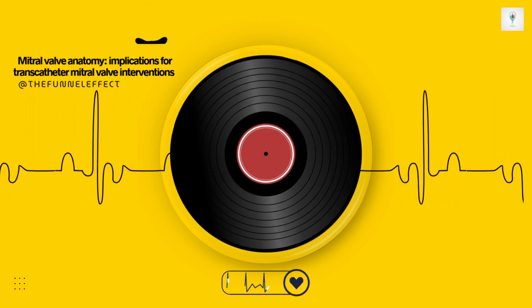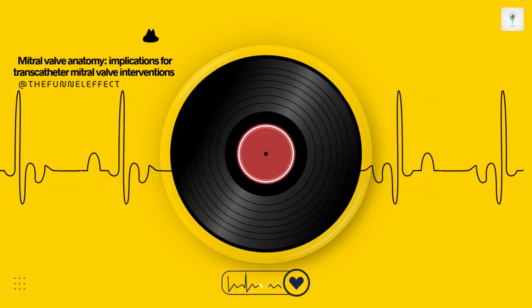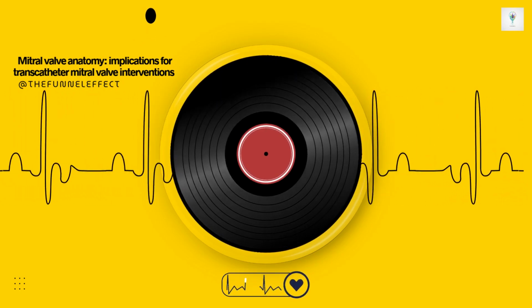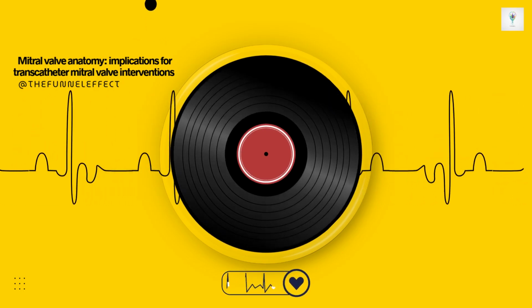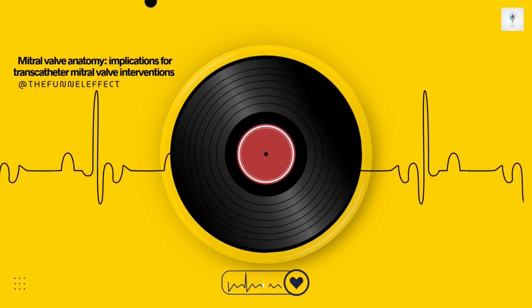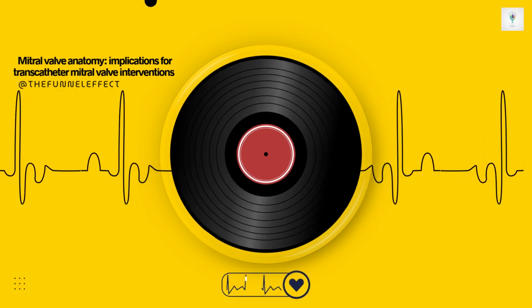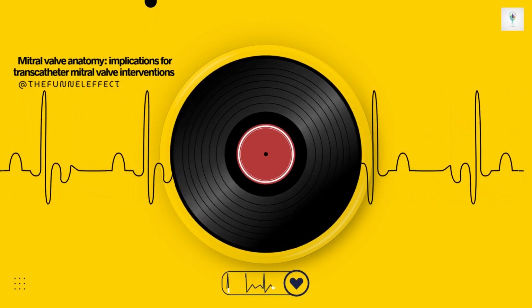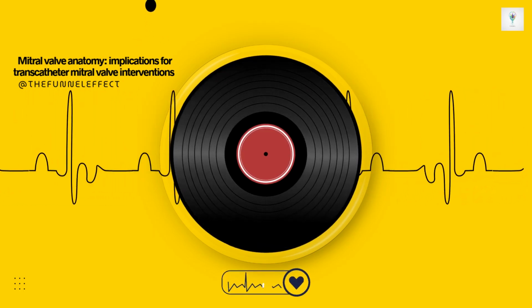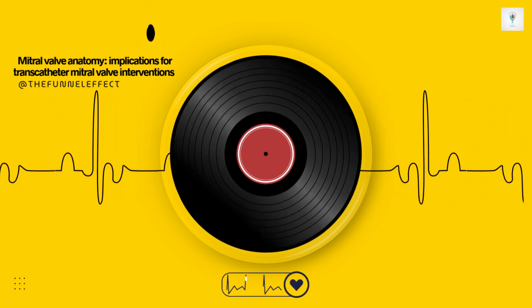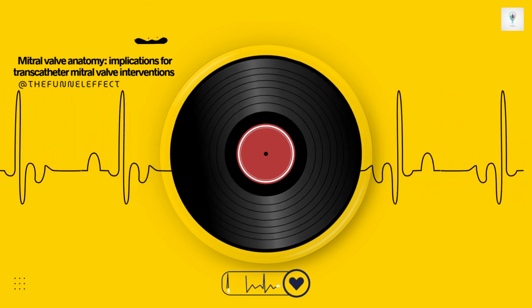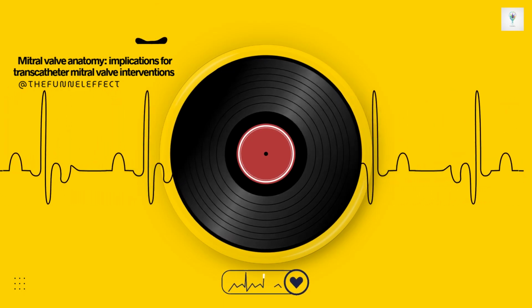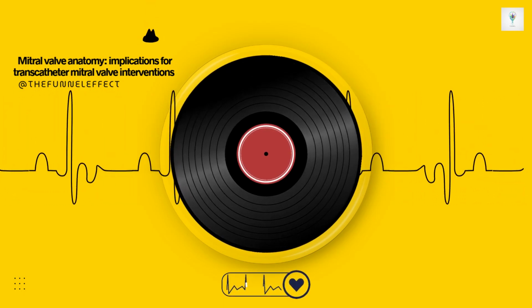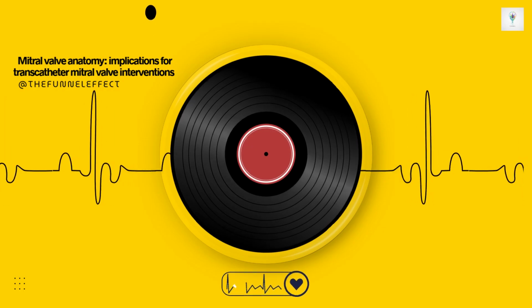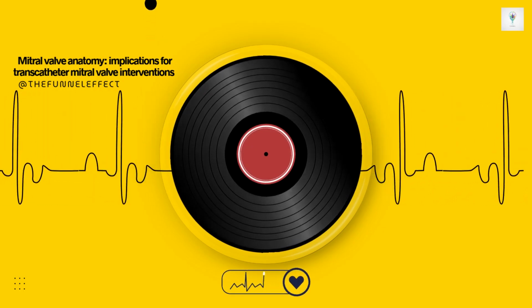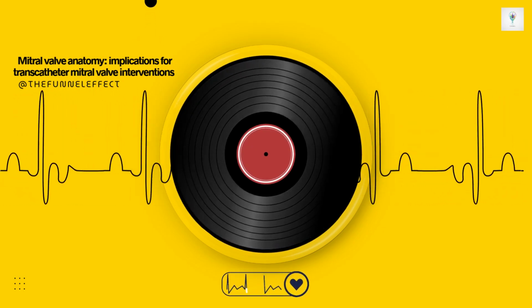The MV annulus is D-shaped, not circular. It's highly dynamic, changing shape and size constantly. It's saddle-shaped, non-planar. And especially posteriorly, it lacks firm, fibrous tissue to anchor into. So getting a prosthetic valve to sit securely and seal perfectly in that moving asymmetric ring is tough. Extremely tough. You need significant radial force from the valve frame to hold it in place, but too much force risks damaging surrounding structures. Finding that balance and achieving a durable seal without migration is problem number one.